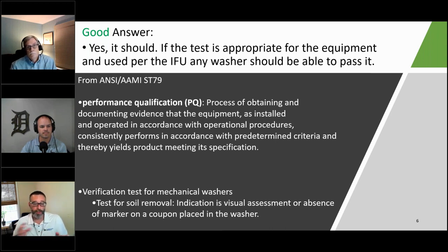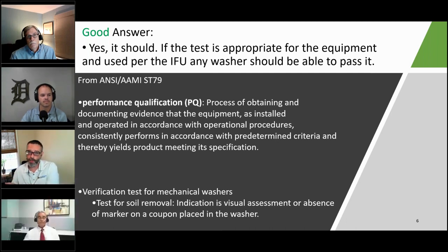Now I did say washer, but the reason this is so wordy is it's going to be different for an ultrasonic, let's say, and it could be different for a cart washer, unless that cart washer is used as an instrument washer, and then it should be the same as an instrument washer, right? That's what we're trying to drill down to here. What is an appropriate test? Well, it depends on the equipment, and if the equipment and the tests are appropriate, then they should pass.